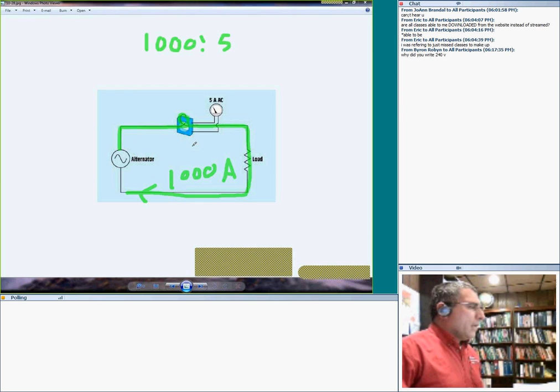So if you put 2 turns, as we said, instead of one wire there are 2 wires coming through the loop - it comes through once and then again, twice. Now suppose you loop it 4 times, you divide 1000 by 4. That will get you a range of 250 to 5.